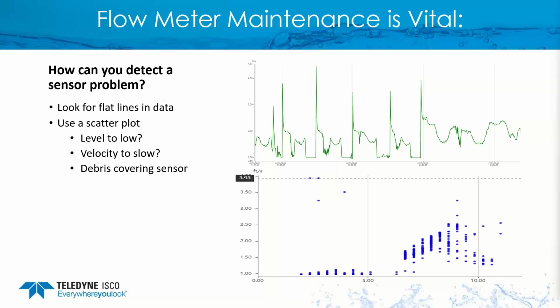Some things that could cause a flat line in your velocity readings: maybe the level's too low, because AV sensors need about 1 inch of water or more to be able to transmit their Doppler signal and get a reading. So if the level drops too low, your velocity is going to drop out, or possibly the velocity is too slow. A lot of velocity sensors, if you get less than a half foot per second, struggle to tell the difference between the signal and noise, and it may drop out the signal.